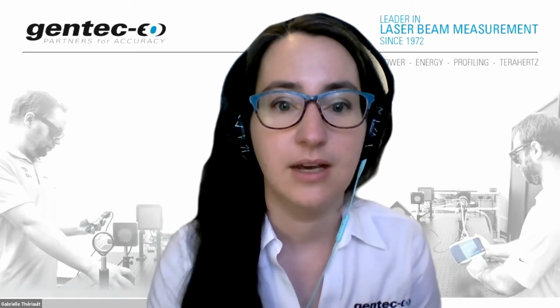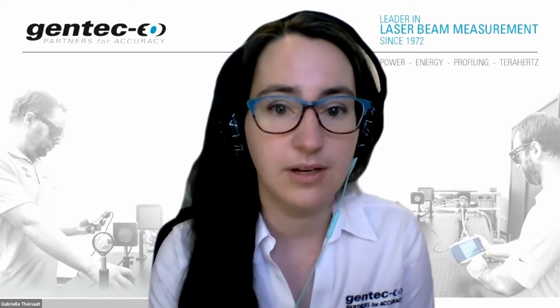So how much inaccuracy can I expect if I measure power or energy with a laser beam having a diameter of only 5% of the available clear aperture of the measurement device? How much of the detector area is it ideal to use for a correct measurement? And how do you make sure that you're not clipping the infrared beam when demagnifying it for the purposes of covering the whole area of the detector?